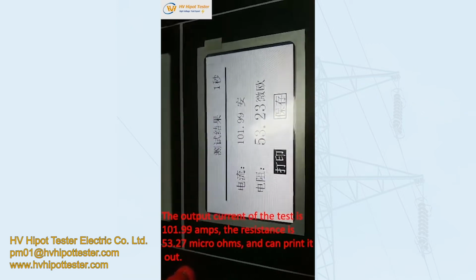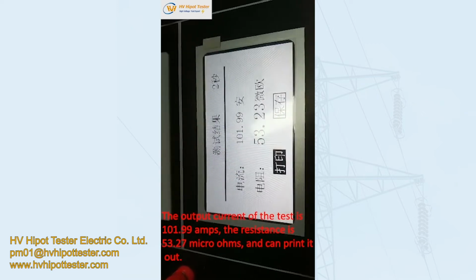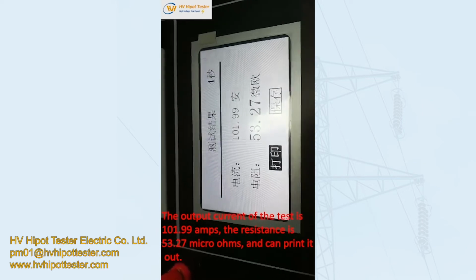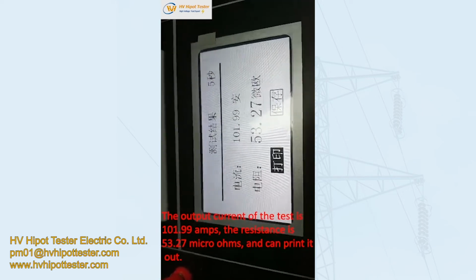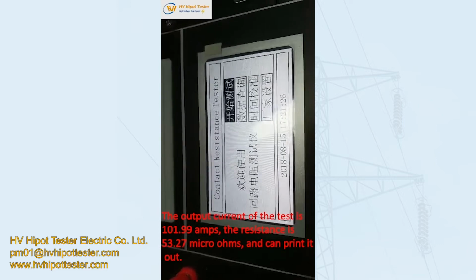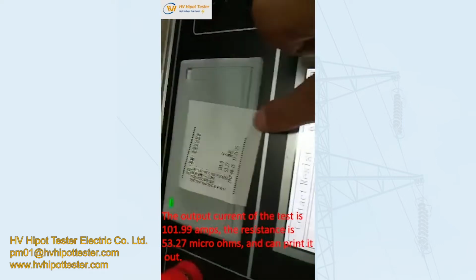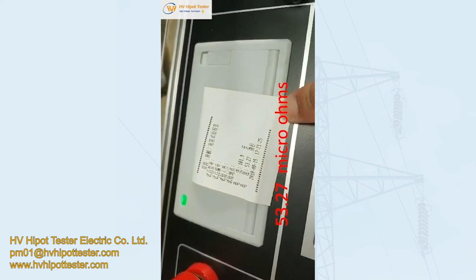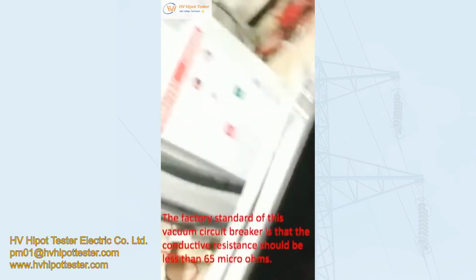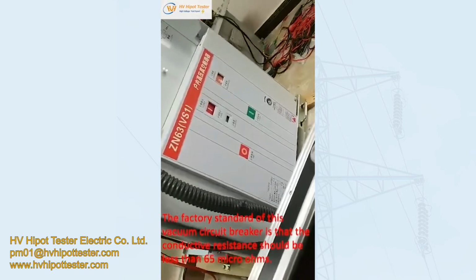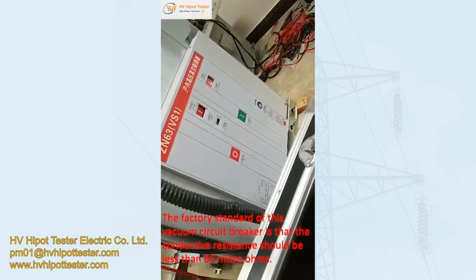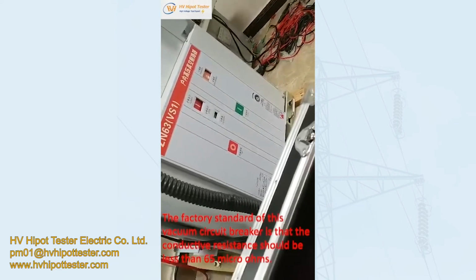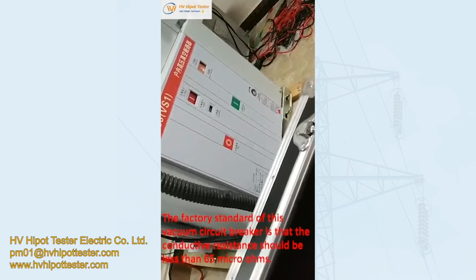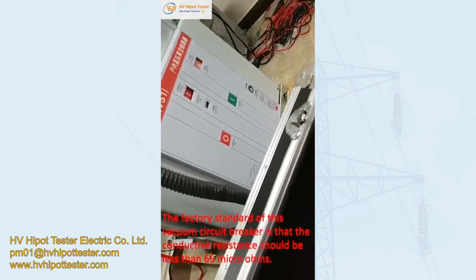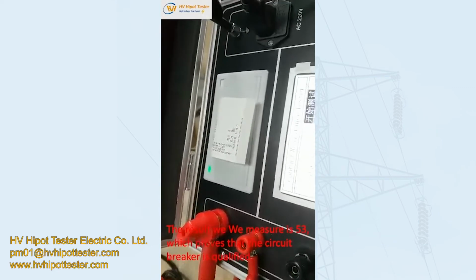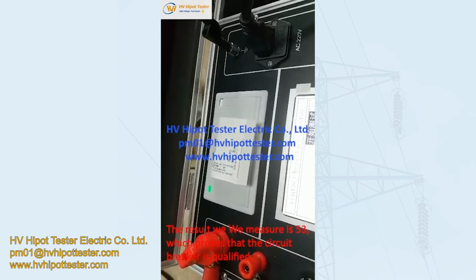The output current of the test is 101.99 amps, and the resistance is 53.27 microohms, which can be printed out. The factory standard for this vacuum circuit breaker requires conductive resistance to be less than 65 microohms. Our measured result is 53, which proves the circuit breaker is qualified.